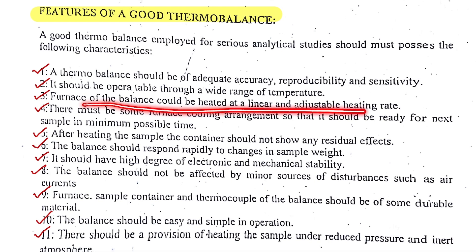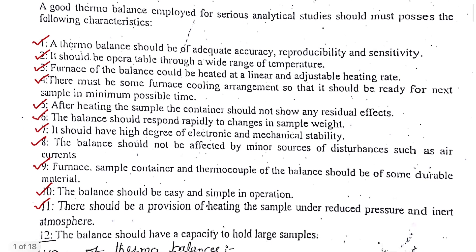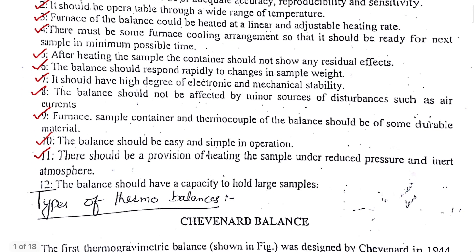The furnace of a balance should be heated at a linear and adjustable heating rate. As we start from low temperature to high temperature, the heating area in which the sample is heated should increase at a linear rate with small increments, and we should have adjustable settings for that heating rate.